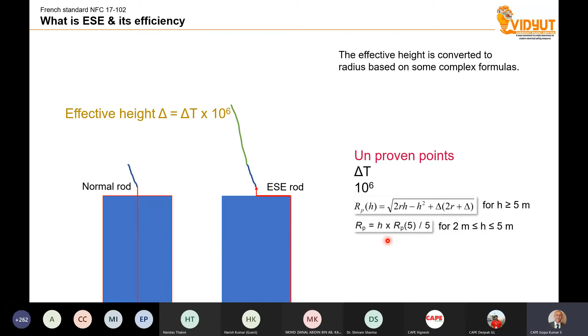Then the speed of the early streamer, 10 to the power of 6, because nowadays there are some reports which say that with the latest high-speed modern cameras, people made some research, and the speed is not 10 to the power of 6, it is sometimes 10 to the power of 4 or 10 to the power of 5. Then these formulas given in the French standard, these 3 points, the delta T, 10 to the power of 6, and this particular calculation are so far unproven. Because when somebody says that I have a new formula, it is the responsibility of the person to show that his formula is correct. Until now, the ESE vendors are unable to prove this particular formula.